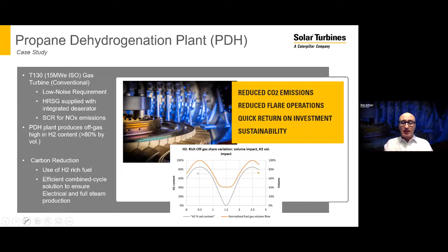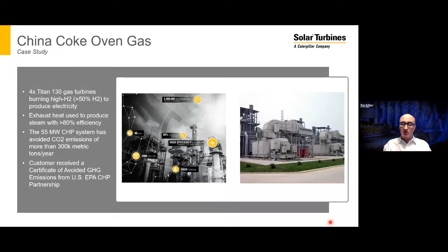Last one for the case study is the example of the coke oven gas industry. As I said before, we have more than 2 million operating hours on those applications. The plant we're showing here has 4 Titan 130 gas turbines. It's a 55 megawatt electrical plant, and very efficient, more than 80% thermal efficiency. Again, using a gas that is between 55-65% content of H2, with a high level of contaminants, so very interesting applications.